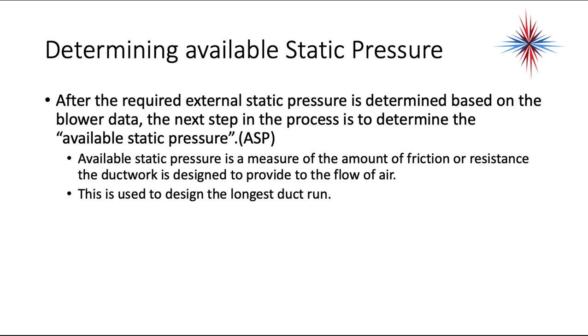After the required external static pressure is determined from the blower data, the next step is to determine the available static pressure. Available static pressure is a measure of the friction or resistance in the ductwork designed to provide airflow, and it is used to design the longest duct run. Everything we do is based on the longest duct run from the air handler — which may not be the longest physical distance, because you must look at the actual length of ductwork including the number of fittings.